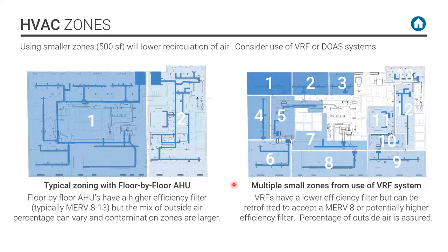Now we'll get into a little HVAC design about zoning. We took a floor in a building and asked, what if you put in two air handling units, one for this side of the floor and one for that side, versus what we call a DOAS or a VRF system, which is a smaller system that deals with smaller zones. Let's say you're in zone four. If someone is sick in zone four, the air is just recirculated in that one zone, whereas with the air handling units, all the air goes back to the air handling unit.